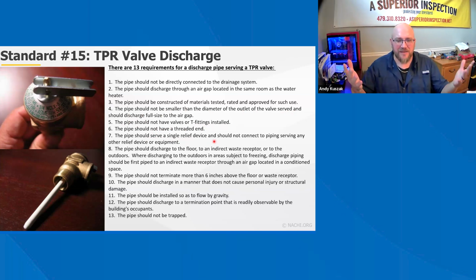So if you have two water heaters side by side that are in series, you cannot pipe those two together and then pipe them into the drain. They have to be individually piped. The pipe should discharge to the floor, to an indirect waste receptor, or to the outdoors. Where discharging to the outdoors is in areas subject to freezing, the discharge pipe should first be piped to an indirect waste receptor through an air gap located in a conditioned space. This is definitely a new standard, because on older homes this is not happening. They just pipe directly to the exterior.